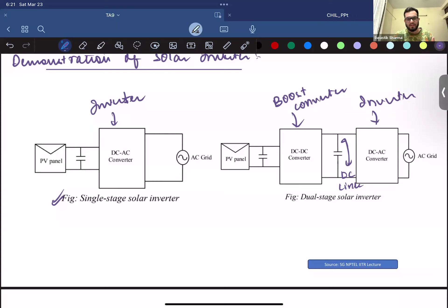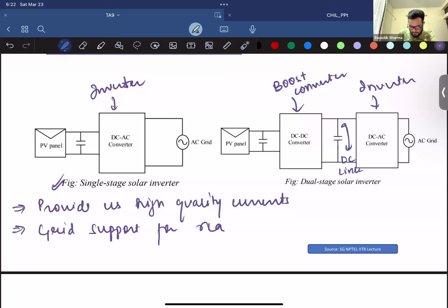Basically, the solar panel gives us DC output, and since we want to synchronize with the grid, we need AC power. The solar inverter needs to provide high fidelity, high quality currents—the total harmonic distortion (THD) of these currents should be minimum, usually below the industry standard of 5%. We also use the solar inverter to provide grid support in the form of reactive power management.